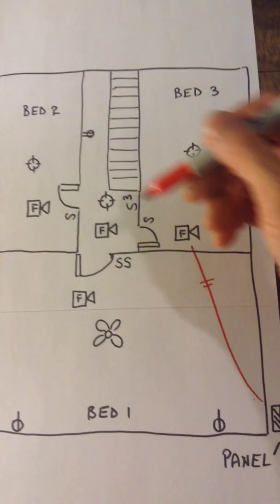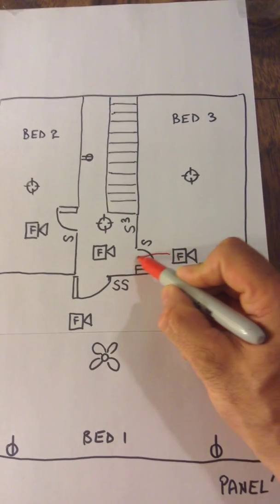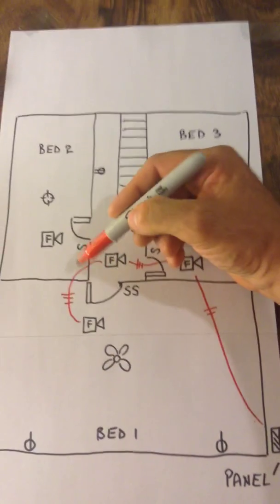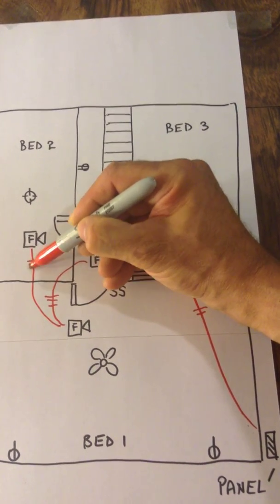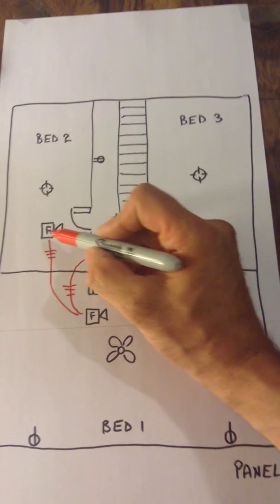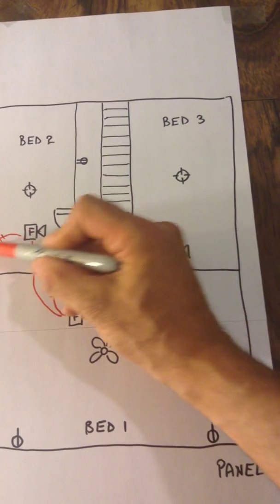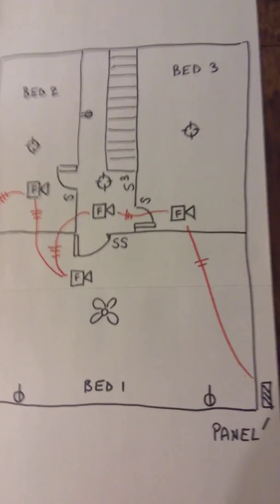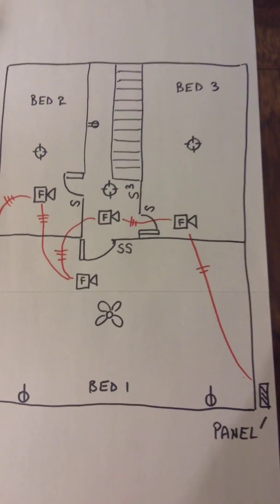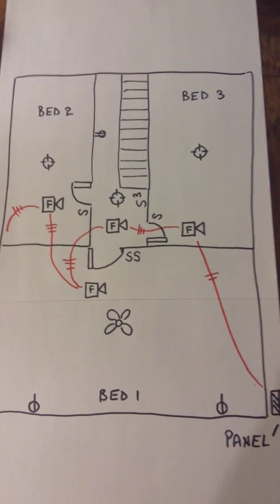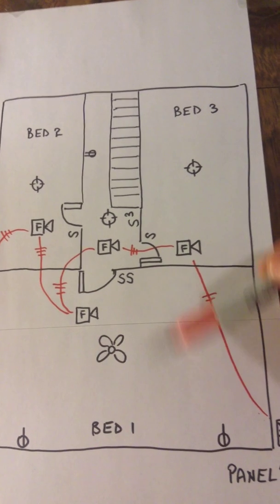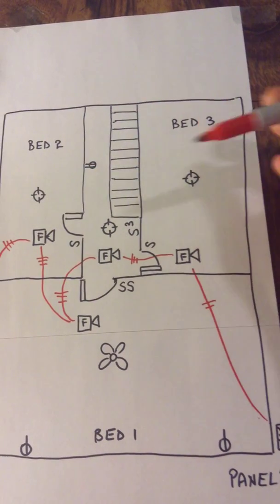Now, smoke detectors need to be interconnected throughout the whole dwelling. So I'm going to proceed forward with 14-3 here, 14-3 over here, 14-3 to each fire alarm. That's going to finish off downstairs. I went to the exterior wall, dropping down into the first floor, ending up somewhere in the hallway. I did that purposely because I'm going to stem off my smokes and feed my bedrooms, lights, what have you. It's going to keep things very short through the stemming process.